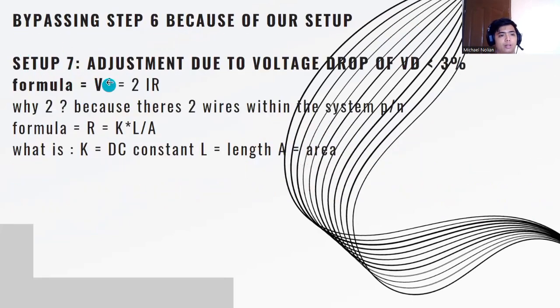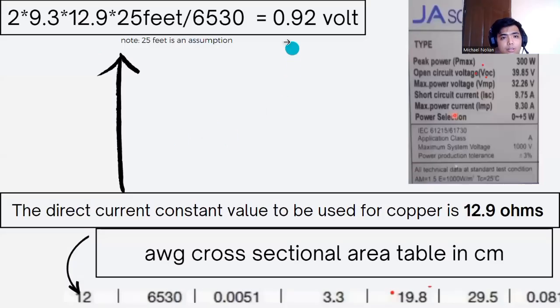Step 7, sorry again: adjustment due to voltage drop of less than 3%. The formula for voltage drop is 2IR. Why two? Because we have two wires, positive and negative, in our system. R equals K times L over A, where K is the DC constant, L is the length, and A is the area. We will see this in the next slide.